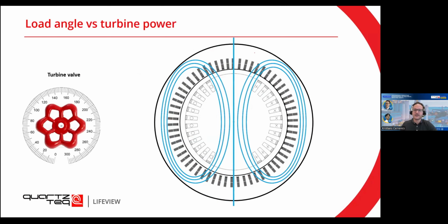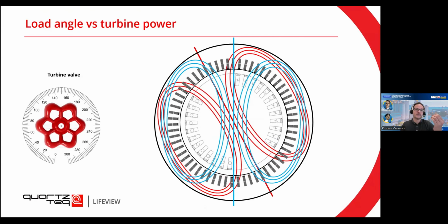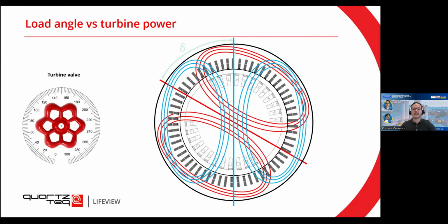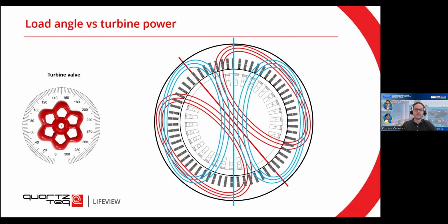However, what we can do is open the turbine valve a little, essentially increasing the steam flow and the mechanical torque. And since the generator is locked to synchronous speed, the rotor cannot spin faster. So it can just shift a little bit ahead by some load angle that is called delta here. And then essentially this uncovers some of the coils for higher sensitivity measurements. So once you do your condition monitoring, it is better to do this monitoring while you go through different loads, because then you are more certain that you're going to uncover a coil and have a more precise measurement.